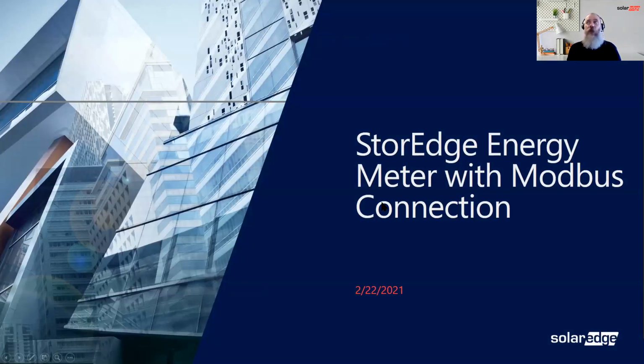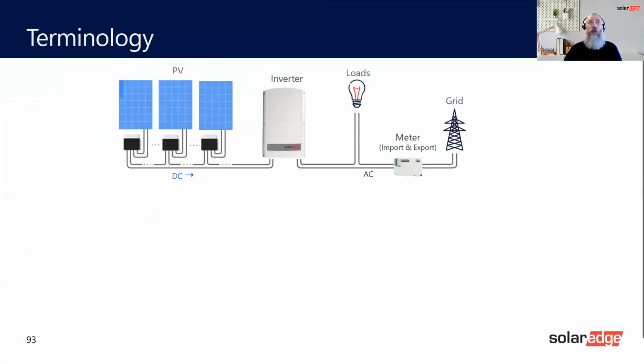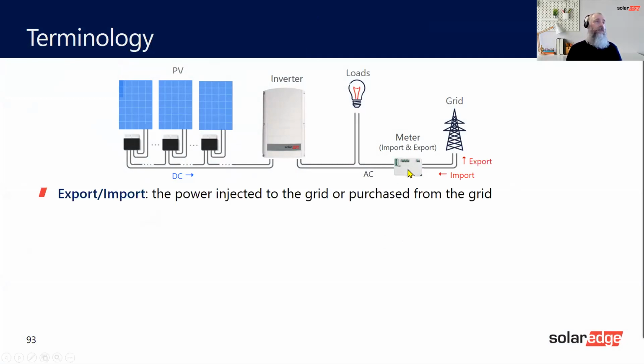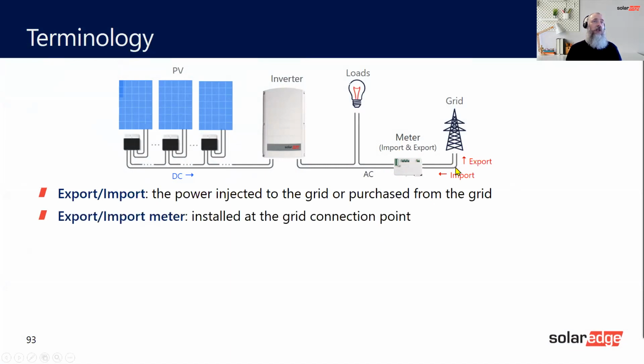So the next one is the SolarEdge energy meter with Modbus connection. This is the meter we've talked about earlier for the storage, and you can see on here it's the same meter. The position of this is at the grid, and the reason we want it at the grid is so we can get the import and export reading from the grid. We don't want it on a load, we don't want it anywhere else. This is where it has to be.